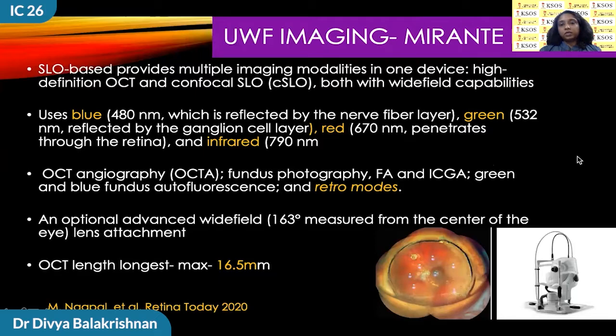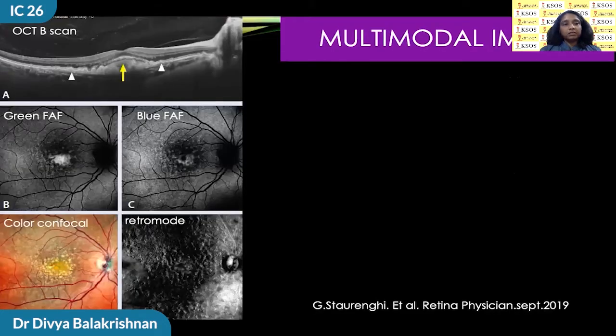Another imaging modality is Mirante by Nidek, which is a newer one also based on the SLO technique, with high-definition OCT and confocal SLO, also capable of acquiring widefield images. It uses four different laser wavelengths to recreate a near-normal fundus image and can obtain OCTA, fundus photography, FA, ICG, green and blue fundus autofluorescence, and retro modes. With an optional widefield lens, it can capture about 163 degrees of the fundus and the longest OCT measurement of 16.5 mm. An example of multimodal imaging by Mirante: OCT B-scan shows hyperreflective material under the RPE and cuticular drusen, green autofluorescence shows hyperautofluorescence at the center, and the retro mode shows extensive involvement at the posterior pole.